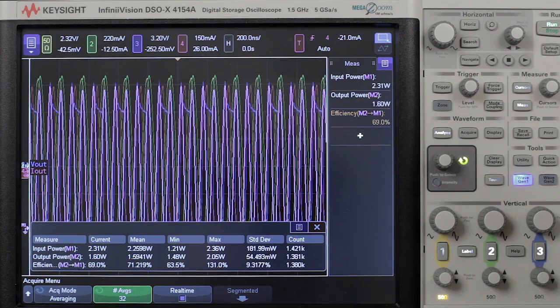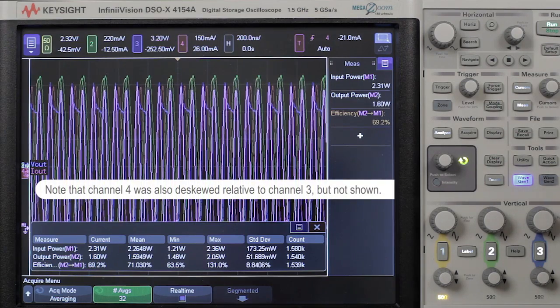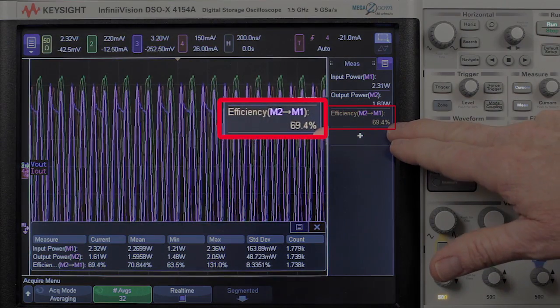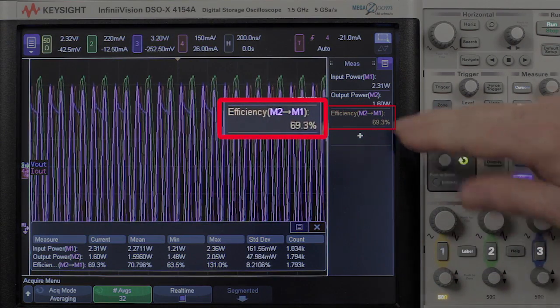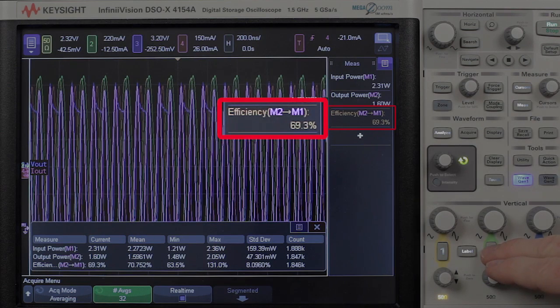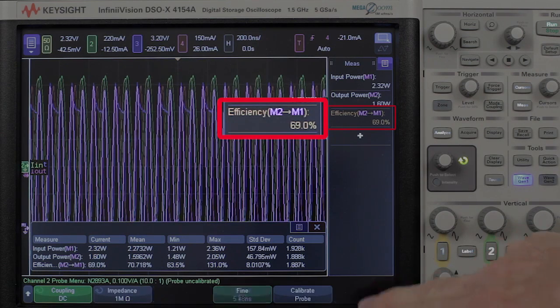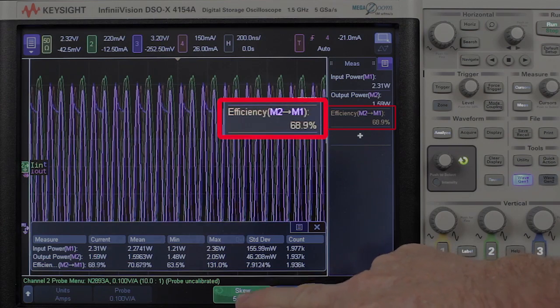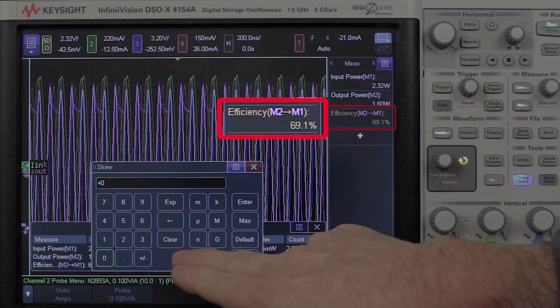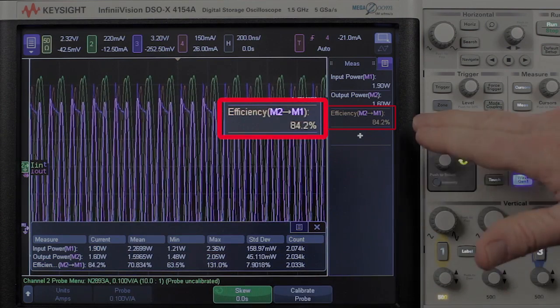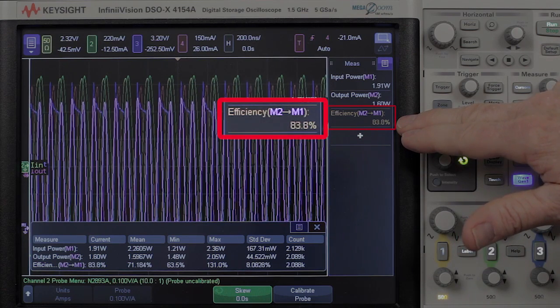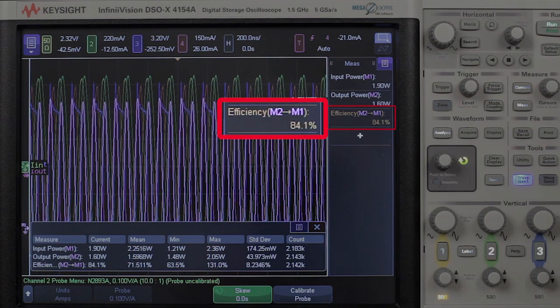Remember, we de-skewed the channel 1 and channel 2 voltage and current probes, and there was a de-skew factor of 5.48 nanoseconds. I'm going to remove that now. So remember, we're measuring, it says about 69%. I'm going to go into the channel 2 menu, which is where the de-skew factor is, and I'm going to plug in 0 nanoseconds. Notice it jumped up to 84%. So if you don't de-skew your probes, you're not going to get accurate measurements.